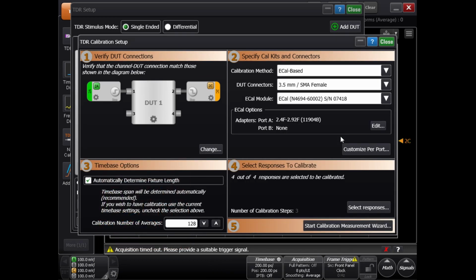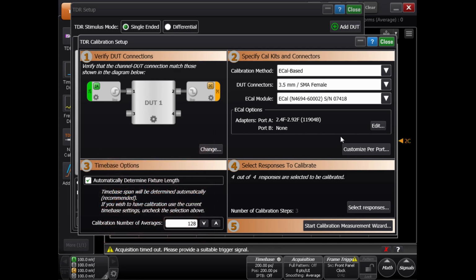Now, if we needed to add any adapters onto our TDR head, which we will, we select that connector, put it on there, but we don't specify that in this calibration. That just needs to be there, as the end of the adapter on the TDR is where the reference plane is. And then we can continue.